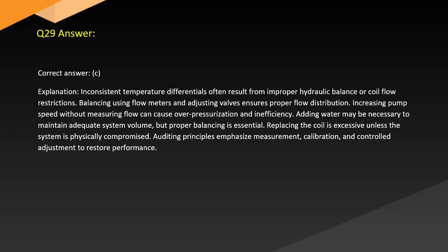Answer. Correct answer. C. Explanation. Inconsistent temperature differentials often result from improper hydraulic balance or coil flow restrictions. Balancing using flow meters and adjusting valves ensures proper flow distribution. Increasing pump speed without measuring flow can cause overpressurization and inefficiency. Adding water may be necessary to maintain adequate system volume, but proper balancing is essential. Replacing the coil is excessive unless the system is physically compromised. Auditing principles emphasize measurement, calibration, and controlled adjustment to restore performance.